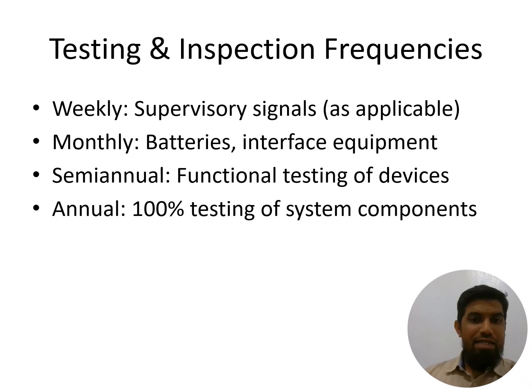One of the interesting topics is testing and inspection frequencies. Chapter 14 of NFPA 72 clearly states the ITMs, inspection, testing, and maintenance procedures, and the frequencies of the fire alarm devices, and the records and the frequencies. Well, a few examples are listed below. Weekly, supervisory signals as applicable. Monthly, we check the batteries and interface equipment. Semi-annual, functional testing of devices. Annual, 100% testing of the system components.